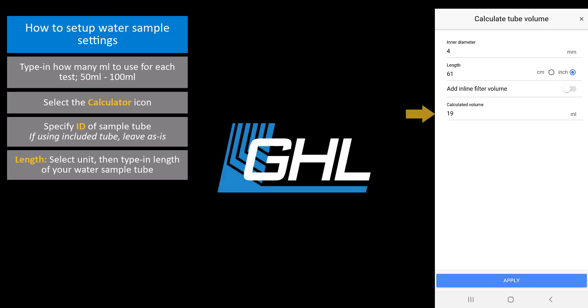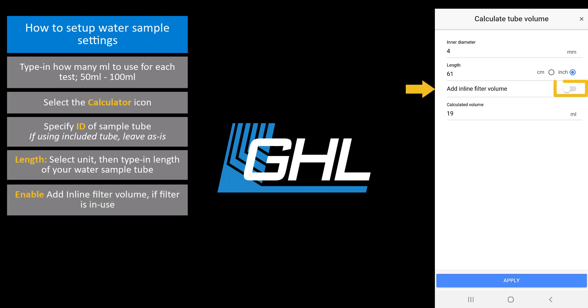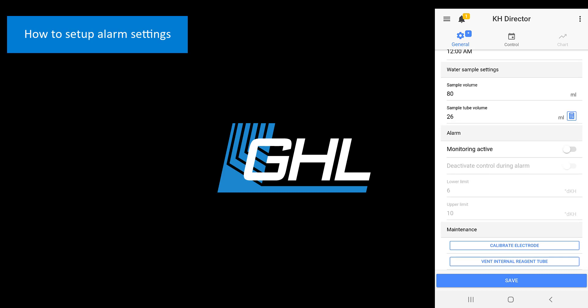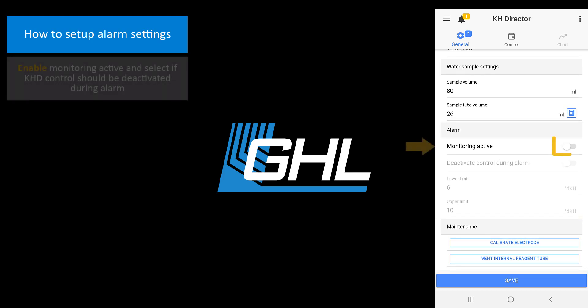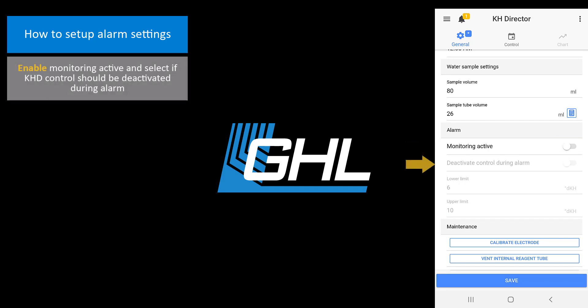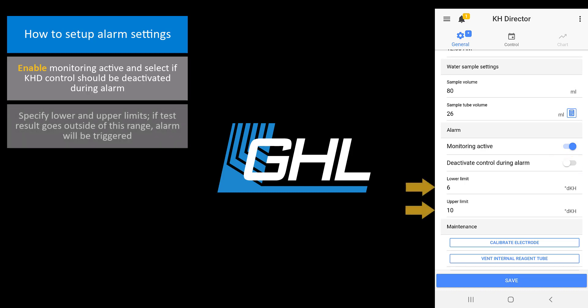You will now see the calculated volume. If you have a water sample filter installed, select this option, then press Apply. Here is where you can choose to have the KHD trigger an alarm in case a test result goes outside of an acceptable range. If you choose to enable this feature, select if all KHD control settings should be deactivated during the alarm. Next, specify the lower and upper limits of the alarm. If any test result goes outside of these boundaries, an alarm will be activated by the KHD.